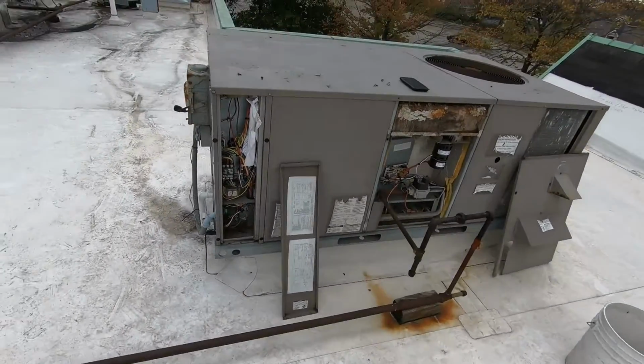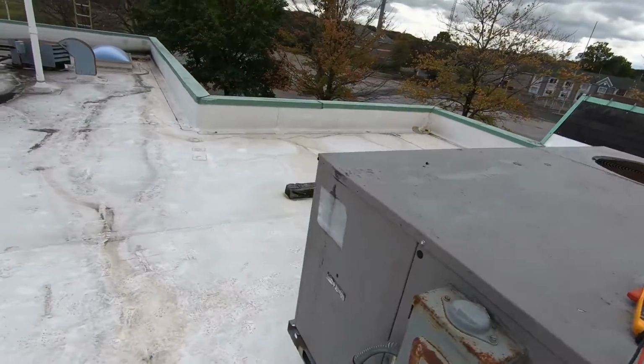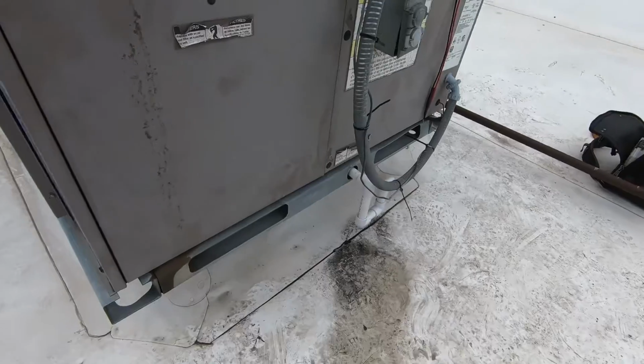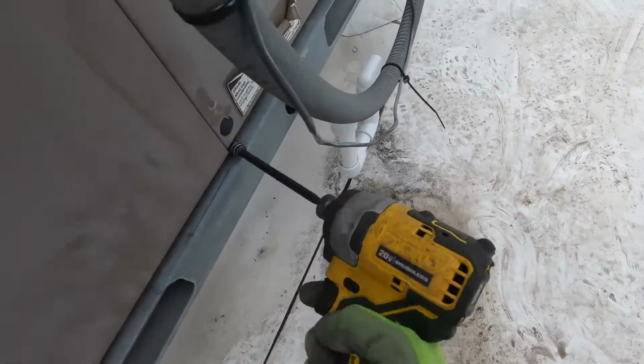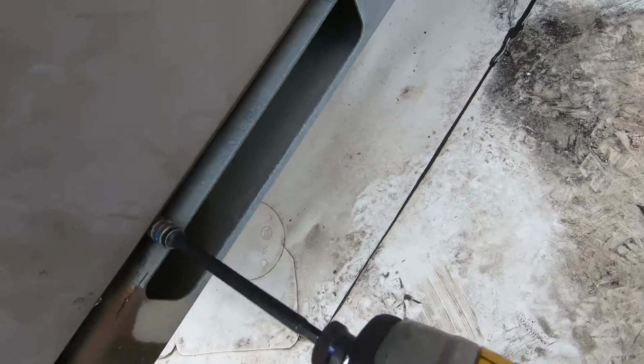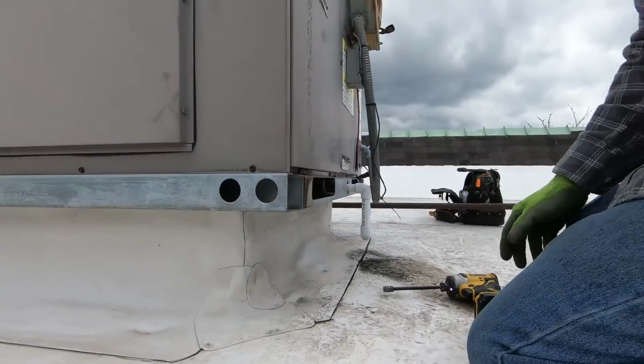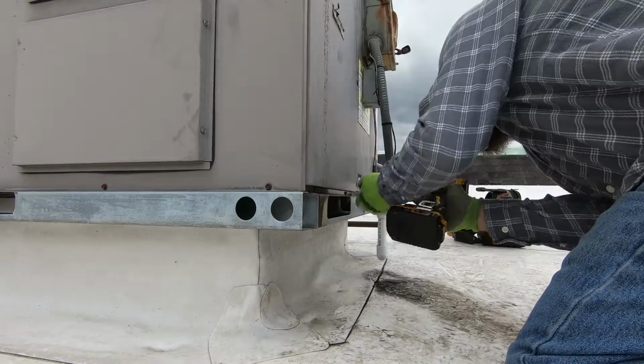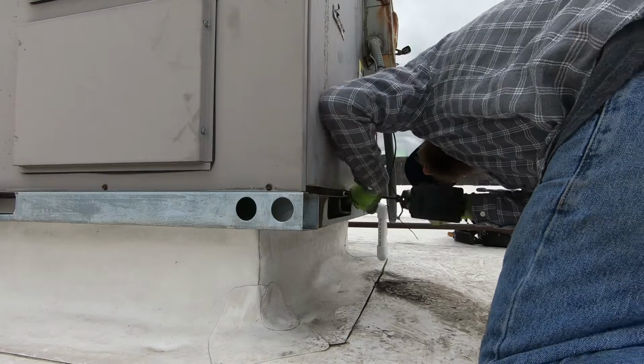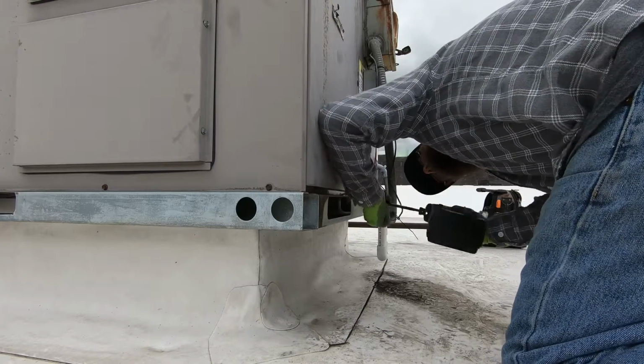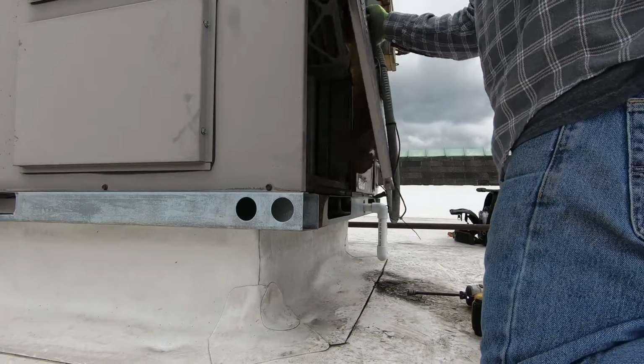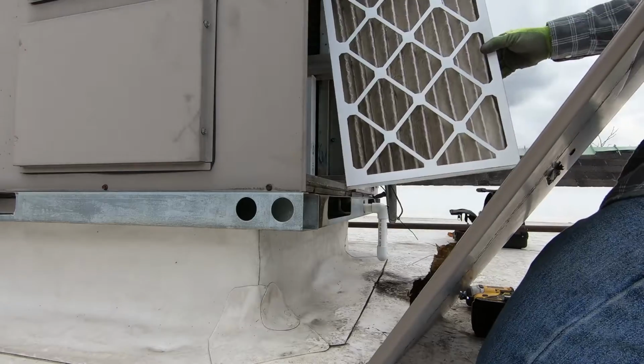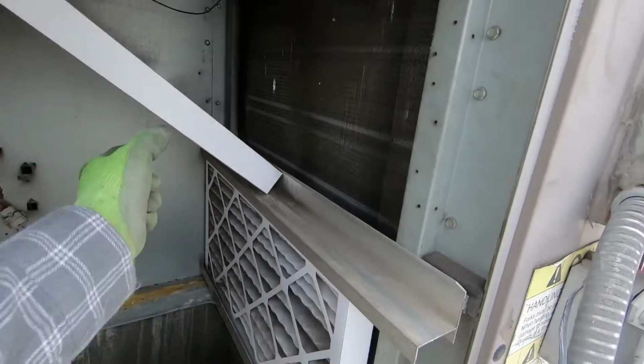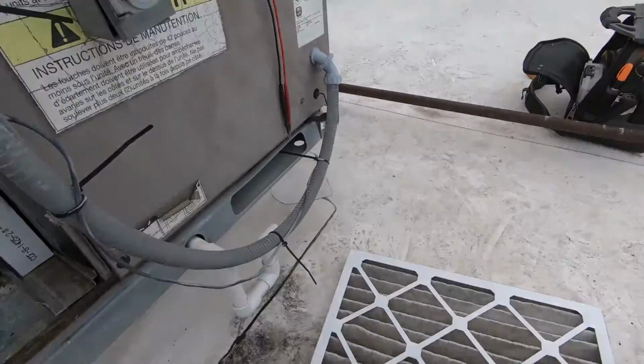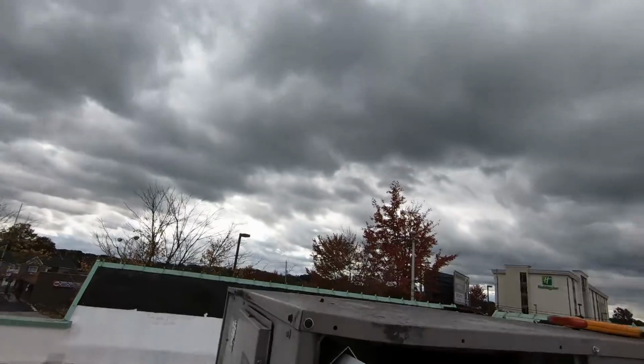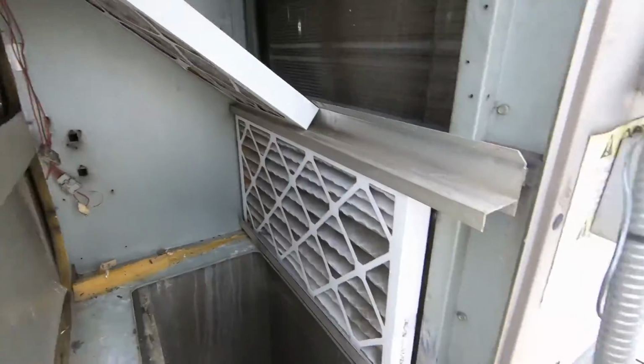All right, guys, heat exchanger looks good. Blower's running. Limits are all closed. Rollout's closed. Let's take a peek at these filters. If I can get my drill in here. Filters aren't horrible. Look pretty good to me. I mean, they're a little dirty, but they're not horrible. Nothing that I would assume would trip the limit.